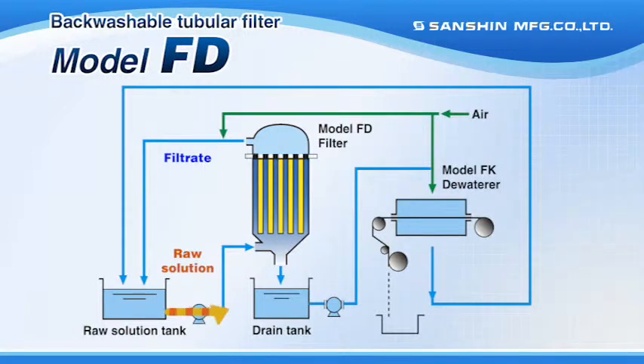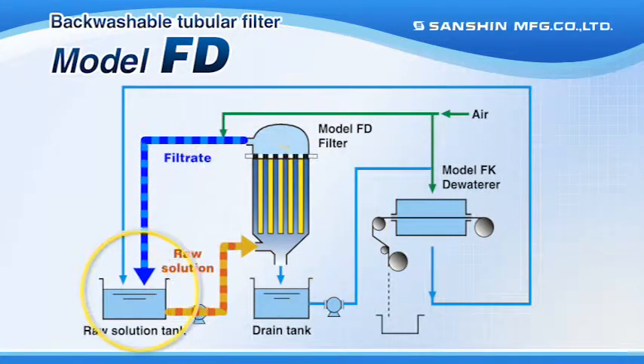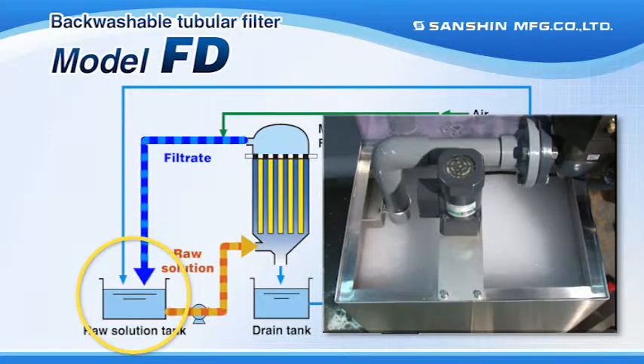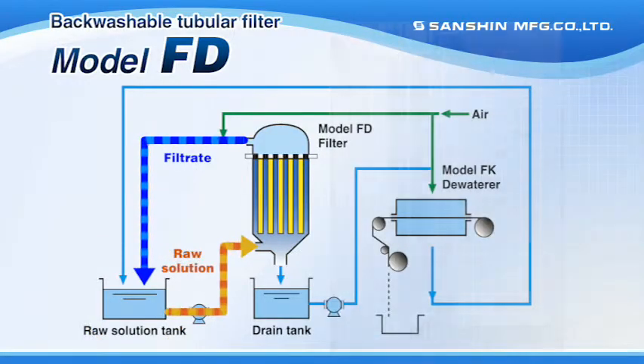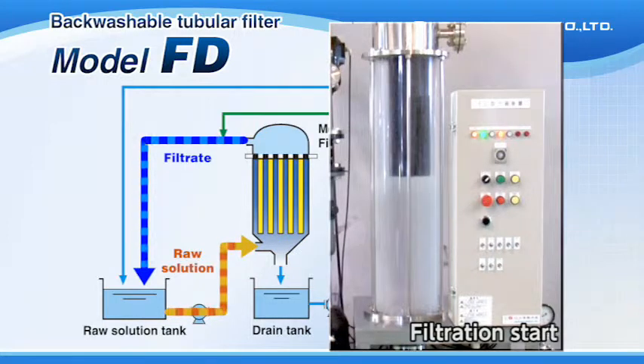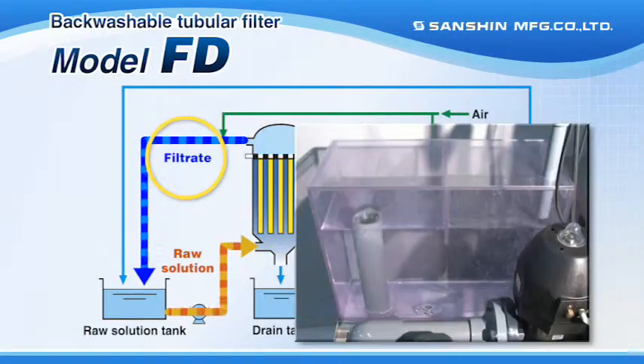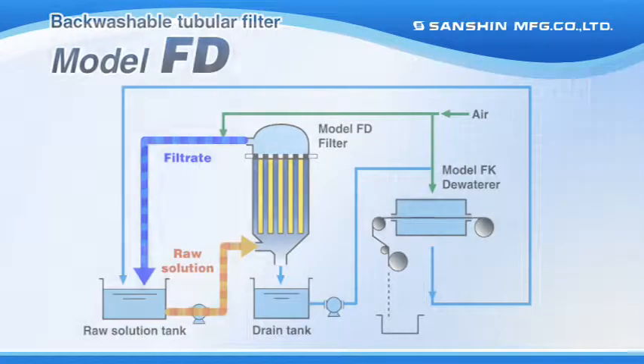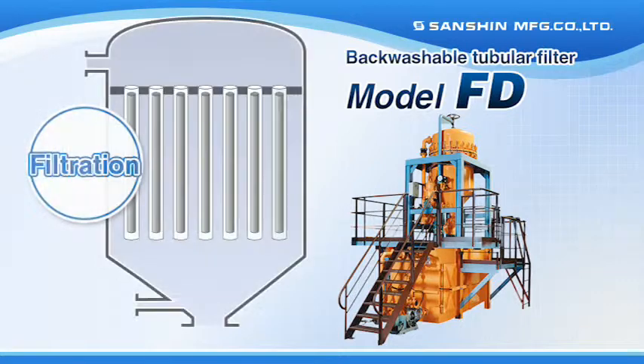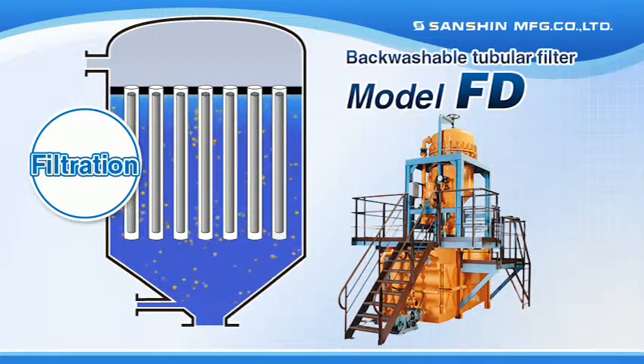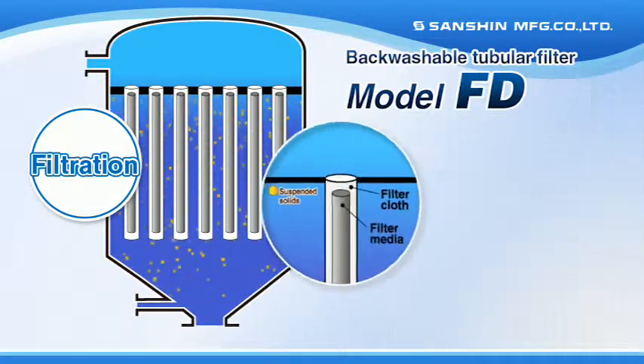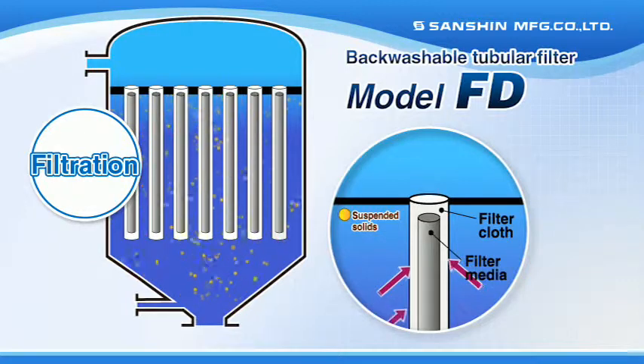Let's begin by taking a look at the filtration processes of the backwashable tubular filter model FD. Model FD filters comprise a raw solution chamber at the bottom of the filter and a filtrate chamber at the top, separated by an intermediate plate. Cylindrical filter media with filter cloth are attached to the intermediate plate for use.